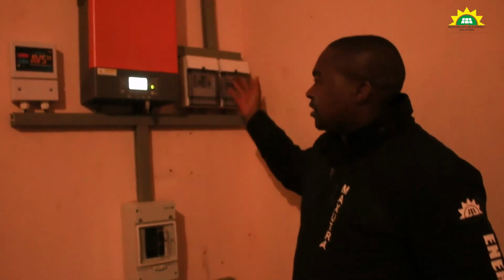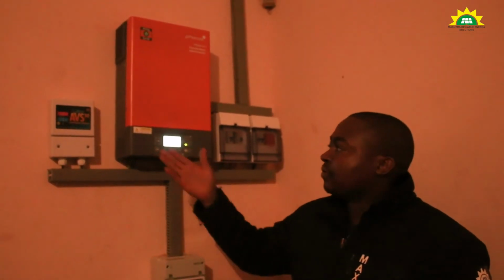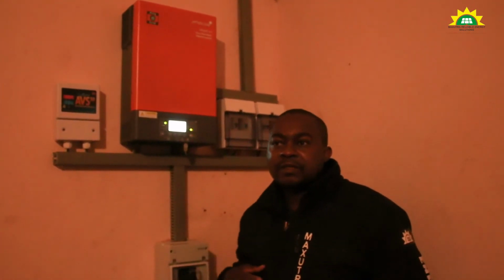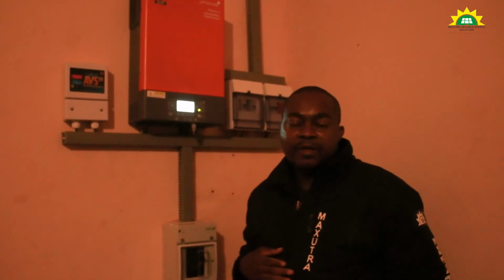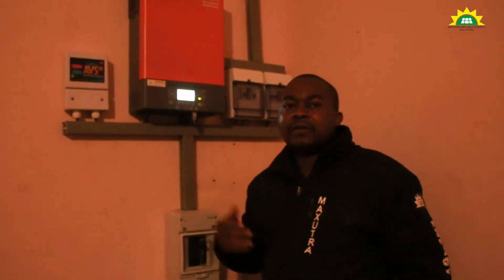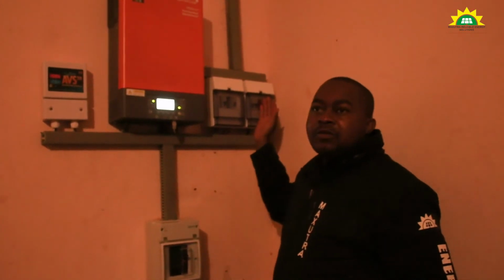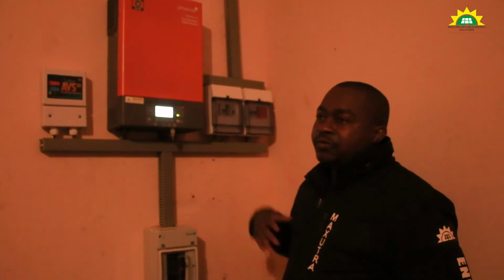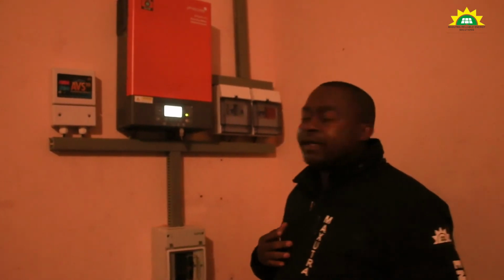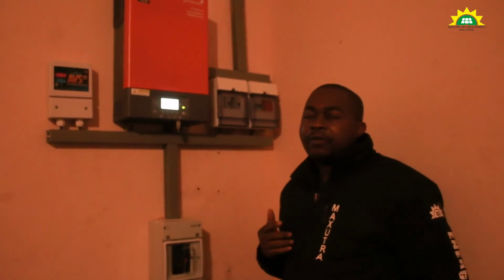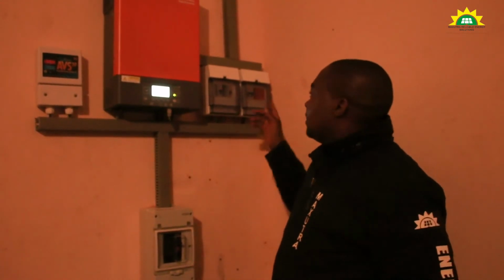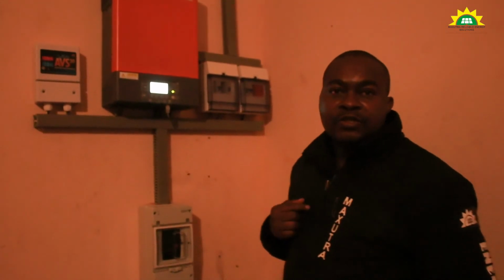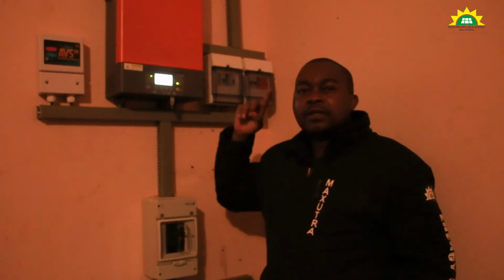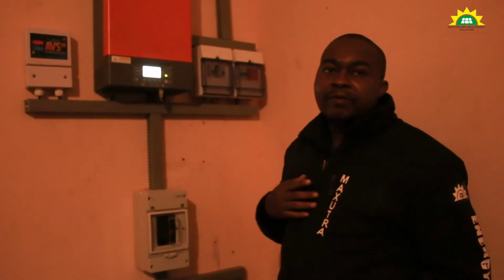Of course, we have put protective measures. This is an AVS, to cater for surge voltages coming from the mains electricity. If there are any voltage fluctuations, the AVS will block that voltage from getting to the inverter. And here, this is the solar array breaker - if there is anything, this should trip. Inside there is also an SPD device, which, if there is a surge coming from the solar panels, especially in the rain season, should earth or direct that surge to ground. So this is a protective device with regards to surges coming from the panels.